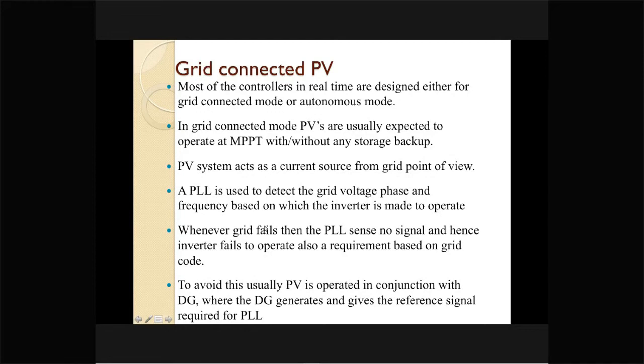This makes the system a little bit more tricky for the Indian conditions. In India, many times the grid fails. No doubt in the urban area we have stabilized it to a large extent, but in the rural area the grid is still intermittent. When it becomes intermittent, the photovoltaic system, even if grid connected, cannot produce power because there is no reference signal coming to the photovoltaic.